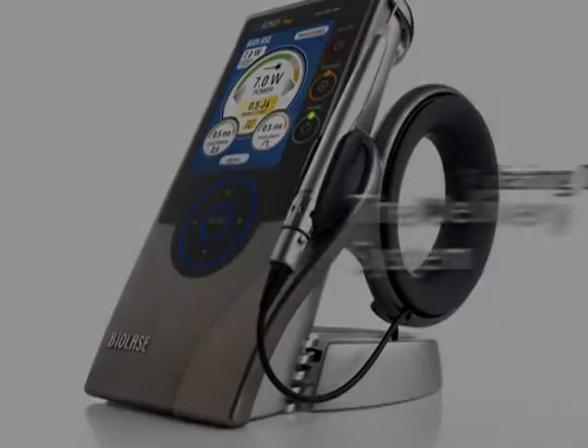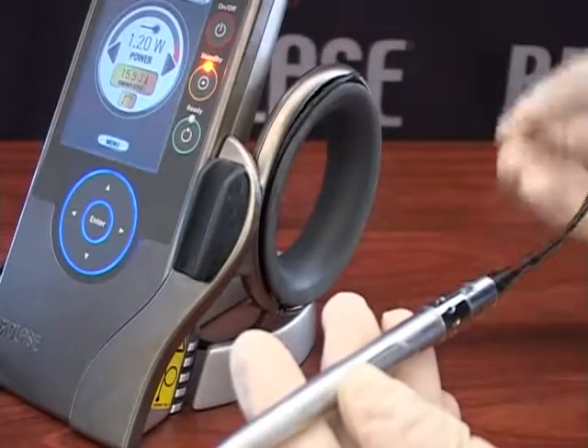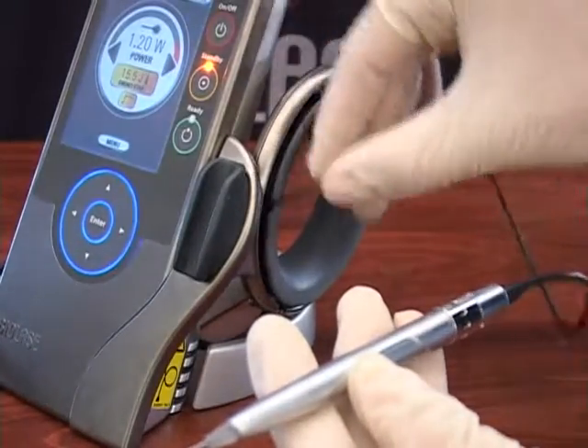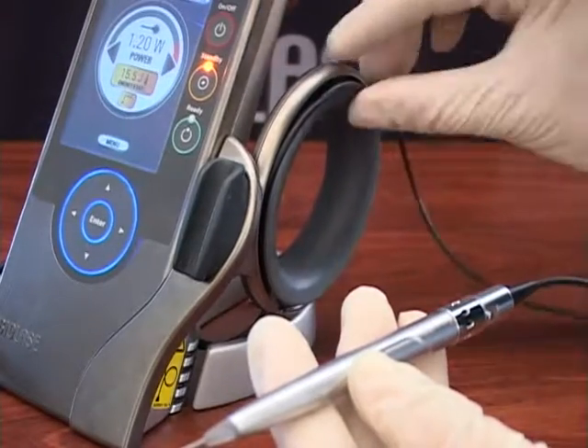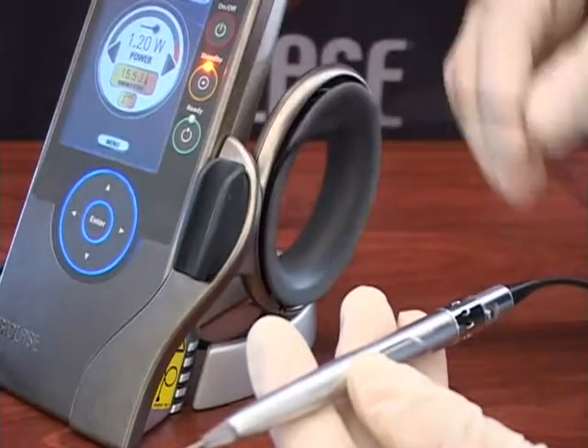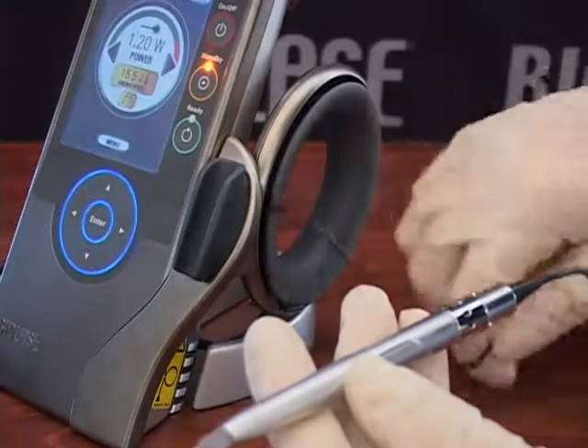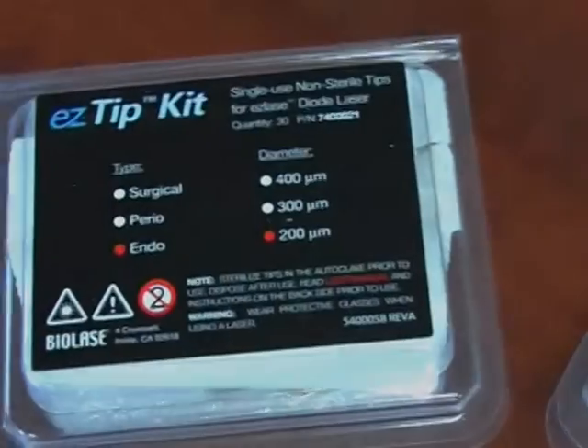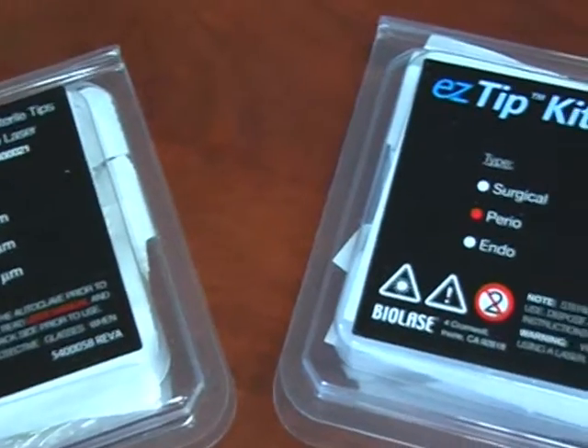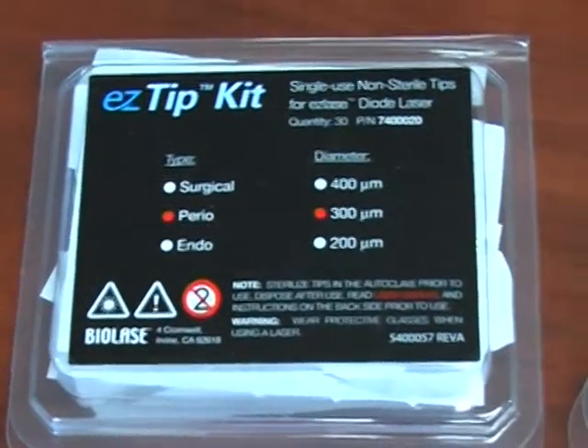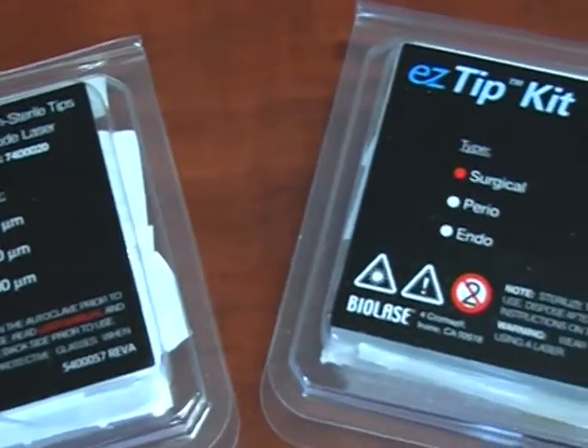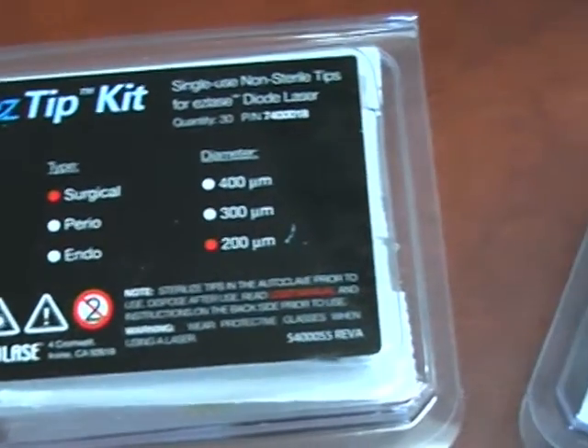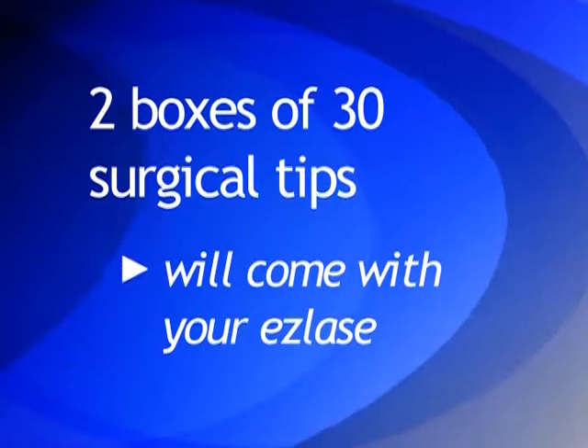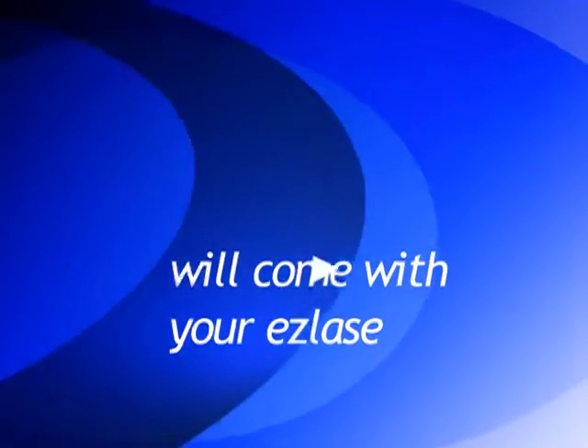The Ezlase has a permanent flexible fiber which carries the laser energy from the main laser unit to the handpiece. Gently pull the fiber from the housing as shown to extend as long a fiber as you need. Non-sterile tips for Ezlase are available in 3 diameters, 400 micron, 300 micron and 200 micron. They also come in 3 different types, surgical, perio and endo. Your Ezlase will come with 2 boxes of 30 surgical tips. Additional tips or tips of a different diameter can be purchased from Biolase customer support.